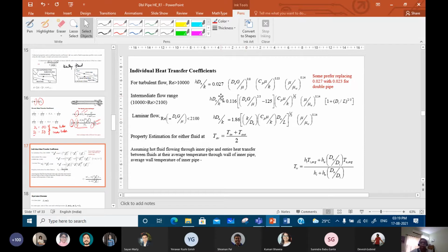But the important part is, we are dealing with heat transfer, right? Now, whenever you are going ahead with these equations, normally if you neglect the Sieder-Tate correction, you might not get an accurate value. So it's very important that you consider, or at least show in your design, that mu average is not very far removed from mu W. For that, you need to evaluate mu W, and it has to be done at the wall temperature TW.